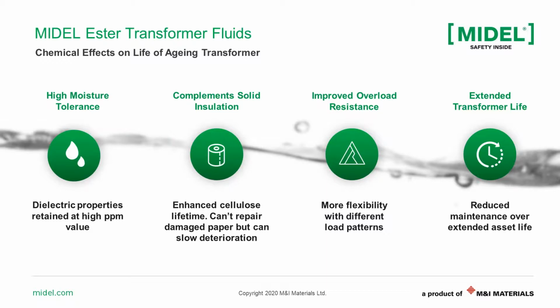As I showed you on the comparison side, you may remember these liquids have very high saturation values, like natural ester at 1100 ppm at 20 degrees C, or MIDEL ester as a synthetic ester at 2700 ppm at 20 degrees C. These high moisture saturation values can be achieved without dramatically changing the dielectric properties of these ester liquids, and this is a good point.